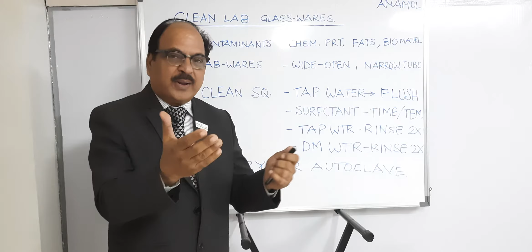When I joined, I said this is not the problem of your chemicals, it's a problem of your glassware, which is not being cleaned properly with the surfactant or cleaning agent you are using, and the boy cleaning it is not cleaning it well. Varying degrees of contamination result in your urease reaction continuing after the incubation time is over. I asked them to address this issue, and the problem which had persisted for so many months got resolved. Apparently nobody bothered to check whether the cleaning solution they were using was good enough.